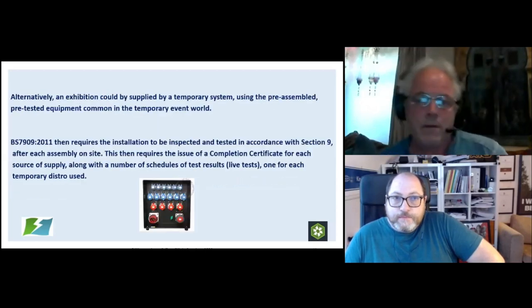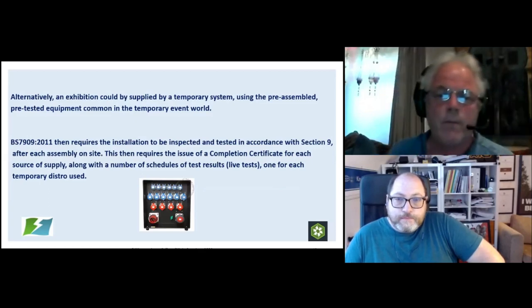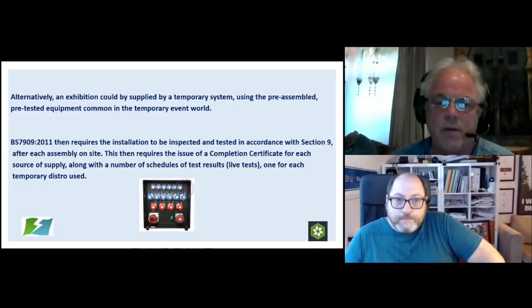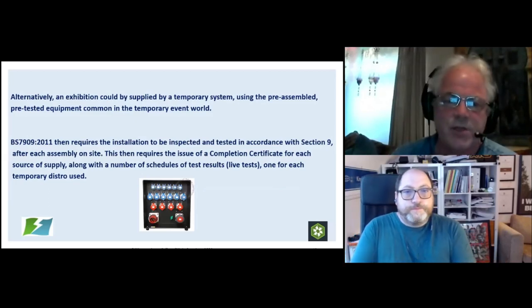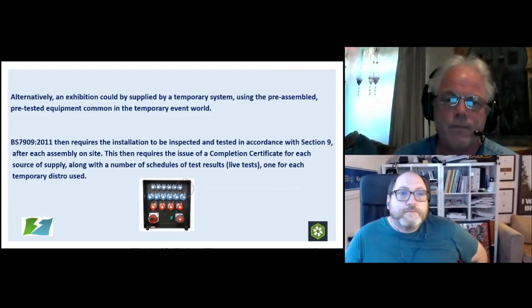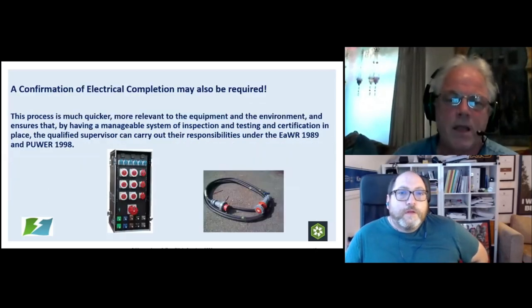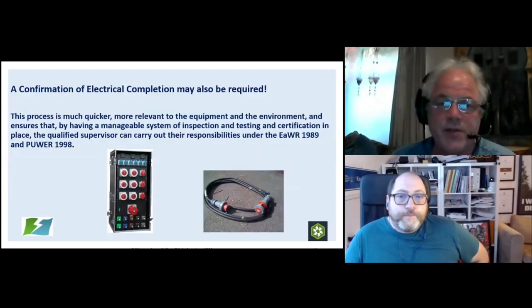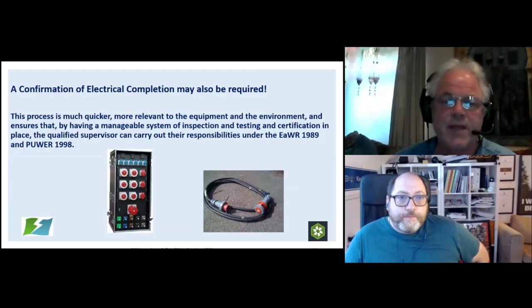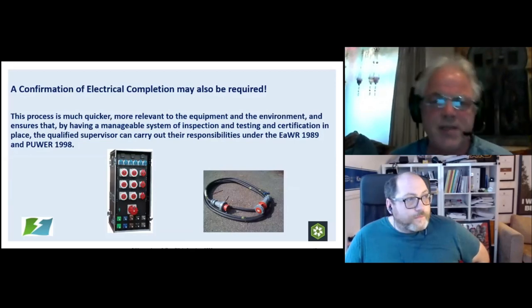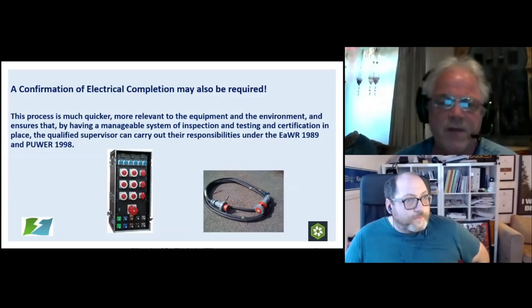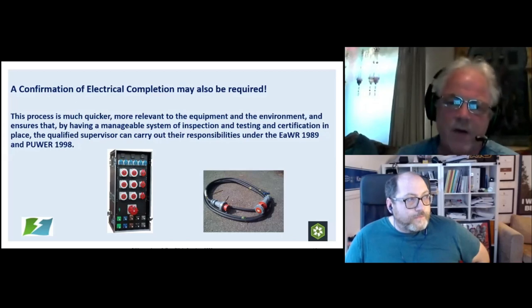So if we use the temporary distro, we can just use a completion certificate and schedule the testing results as per, and it's a much quicker, far easier job. We may also need to do a confirmation of electrical completion when it's all finished, but again, that's a fairly quick process. So the actual installation, the inspection, the testing, the actual putting together of the system, is far easier, far quicker, and far more manageable.